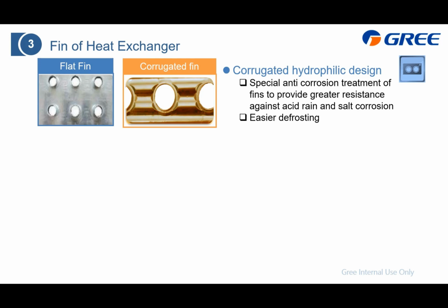And for this one, for heating, if there is ice when we're doing the defrost on the surface of the outdoor heat exchanger, it will become water. And for this corrugated fin, it will be easier for the water to flow out because there's no slip, right? And just due to this one, it will be easier for the defrosting, just compare with the flat fin.